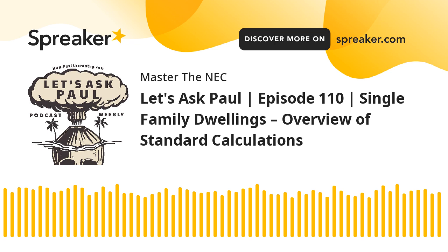Now, you're probably saying, okay, well, what is the VA value that we're going to use? And so that's when you're going to look at 220.52A. And remember, when we're talking 220, we're looking for values as part of a calculation. When we're looking at 210.11, which is to determine the number of small appliance branch circuits, that's just the number of branch circuits. That's a number. But we need to get a VA value, volt-ampere.